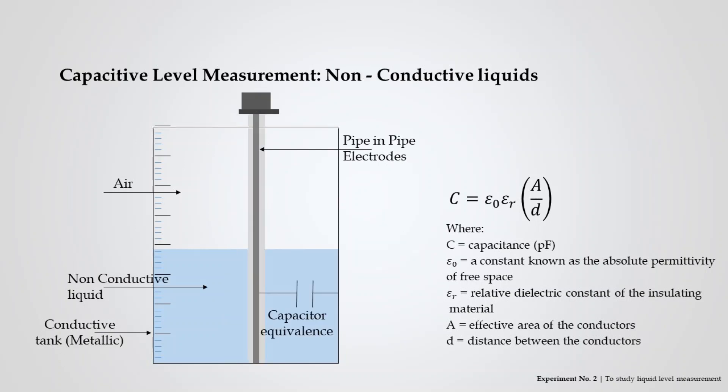The level measurement setup of non-conductive liquids consists of a conductive tank usually metallic in nature. A metal electrode is placed inside the tank. The liquid used for measurement should be strictly non-conductive in nature. The metal electrode and the metallic wall of the tank act as two plates of a capacitor with air and water acting as a dielectric material separating them. The capacitance developed across these two electrodes is represented by the equation shown below. This capacitance is directly proportional to the liquid level in the tank.